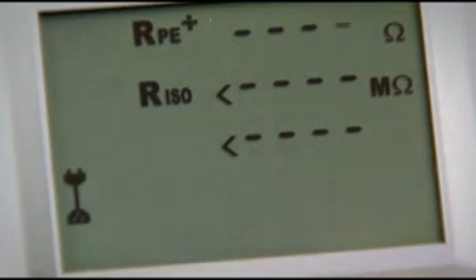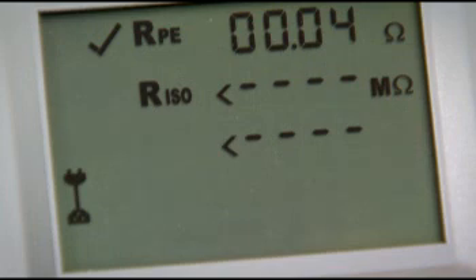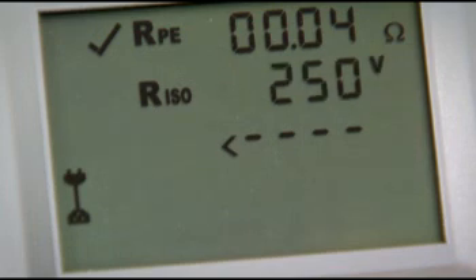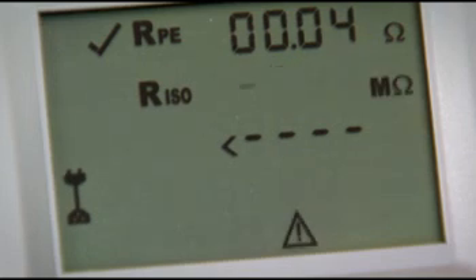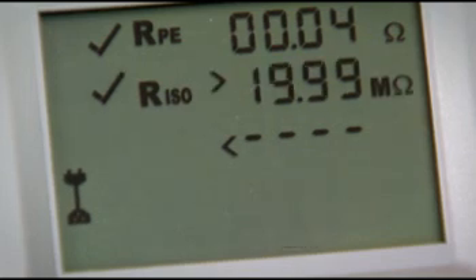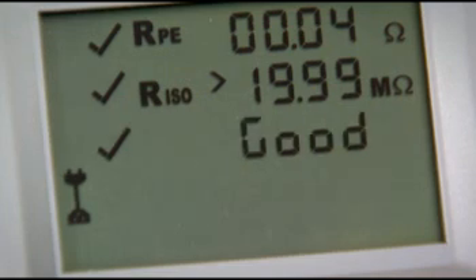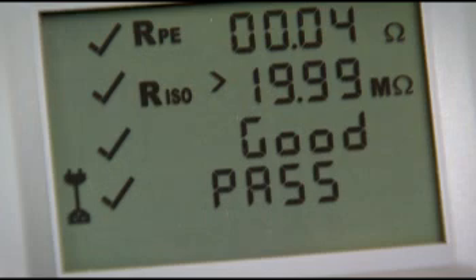The tester automatically detects the fact that it's a cord test and is performing the cord test for us. So it's measuring earth continuity, insulation at 250 volts, and finally it's measuring the cord polarity, which it says is good. Overall result is a pass, so it's a pass for the sequence.